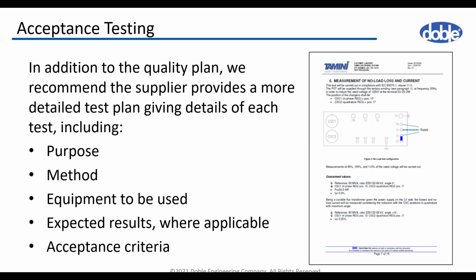It is always preferable, and we advise our clients, to insist that the manufacturer provide a detailed test plan for the factory testing. This is an additional document to the quality plan, where you can find details for the works tests, including the test method used, also measuring equipment, and what the expected result is. In case of a limit, what the limit is. The detailed test plan should also indicate the acceptance criteria, and in case we are not happy with the methodology or the equipment used, we can discuss this well in advance of the factory testing and not lose time in the test laboratory.